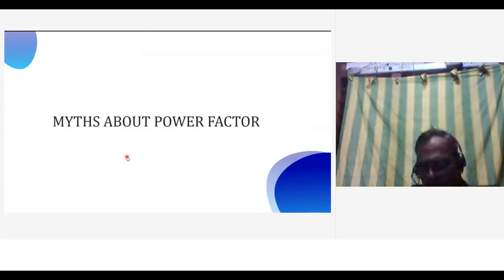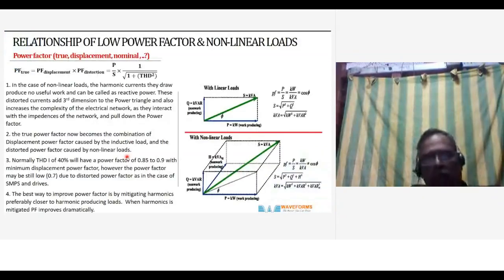There are various myths about power factor when it comes to harmonic load. There's a third dimension added to power factor when there are non-linear loads. As I told you earlier, displacement into distortion is the true power factor. If you see the first diagram, you will see that with a simple linear load, say an inductive load, adding a capacitor, as much as required for the reactive energy, will improve the power factor.